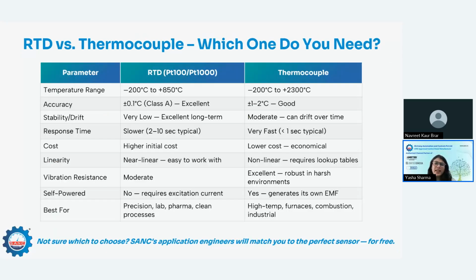Now, I get asked this question multiple times: what should I use, RTD or thermocouple? And my answer is simple: it depends on your application. The first and most important part is temperature range, at what temperature you are operating your furnaces or your process. If your temperature range lies between -200 and 850, then you should go with RTD. But if it is a higher temperature range, from -200 to 2300 degrees, then you should go with thermocouple.